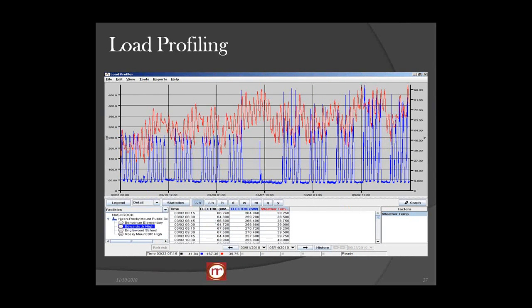Okay, with Automated Energy, I want you to see, this is a middle school that's hot water, chilled water. Notice that during early March, we're still in the heating mode. Look at our kW. We're really camped out around 250. We're doing pretty good. Just as soon as we go to AC, we almost double our kW. That's a lot of money. So what this tells us is we have a bunch of air handlers here, and we don't really have the opportunity to shed like we do at another school with heat pumps and compressors. So what we have is a change in the chiller logic to determine what this kW will be. In other words, make it real simple.